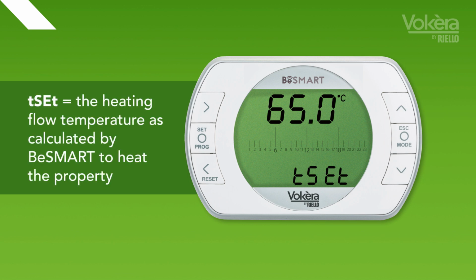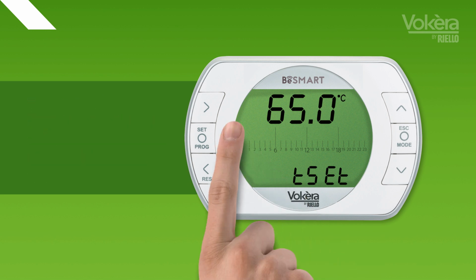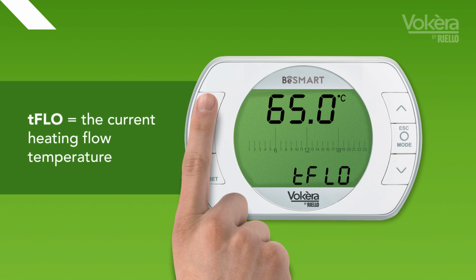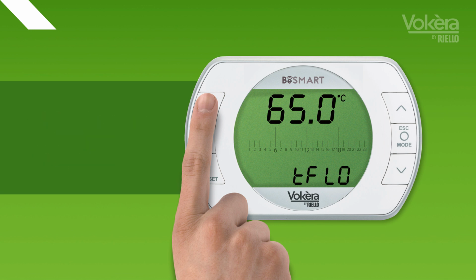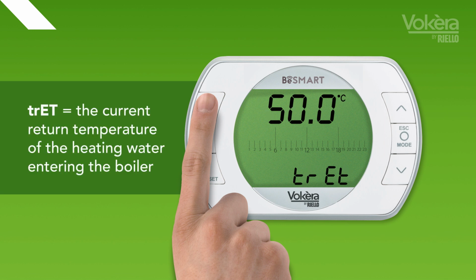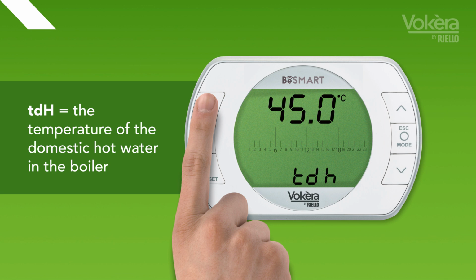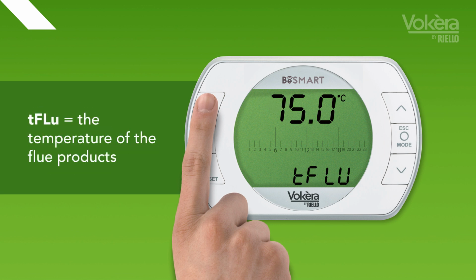T-Set is the heating flow temperature as calculated by BeSMART as necessary to heat the property. T-Flow is the current heating flow temperature. T-Ret is the current return temperature of the heating water entering the boiler. TDH is the temperature of the domestic hot water in the boiler. T-Flue, the temperature of the flue products.